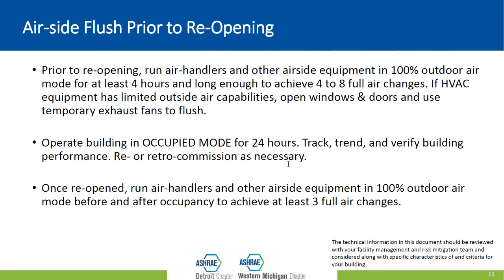After that, you want to operate the building for at least 24 hours, and you want to monitor, track, and trend the building performance. Is it able to maintain set points for temperature? Is it meeting your airflow requirements? Is everything working like it should? Does anything need to be adjusted, repaired, or replaced?